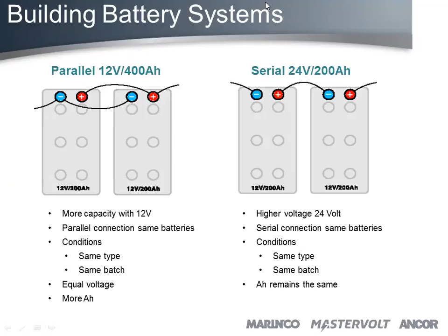When it comes to 24 volt, you have to put the batteries in series to double the voltage, but that does not double your capacity. So it's 24 volt, 200 amp hours. That's where people get confused — they call and say they've got 24 volt, 400 amp hours. No, you don't. You've got 24 volt, 200 amp hours.